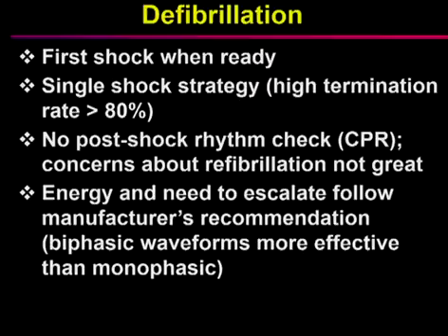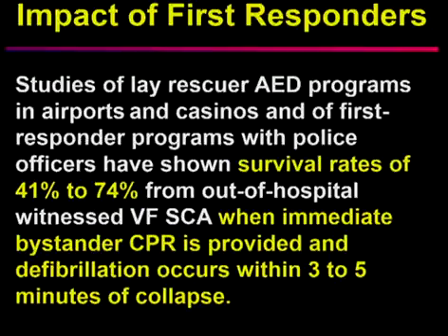That was when we used monophasic waveforms. Any manufacturer today uses biphasic waveforms, and for the same level of energy, the cardiac toxicity is much less. So there's less fear of causing injury, therefore the encouragement to deliver a shock as soon as a shockable rhythm is being recognized.